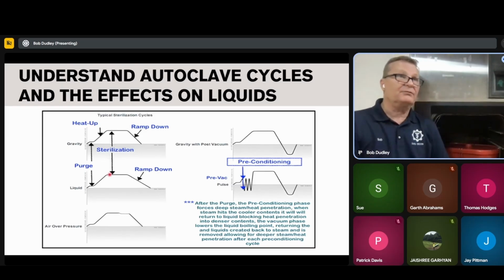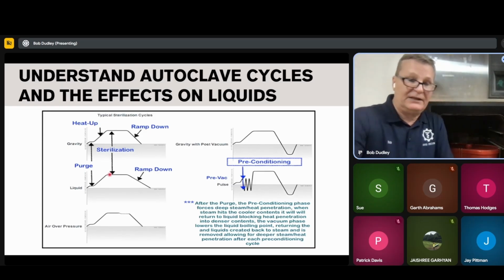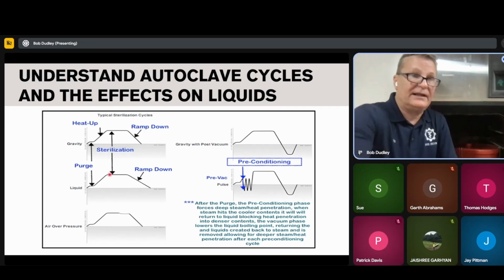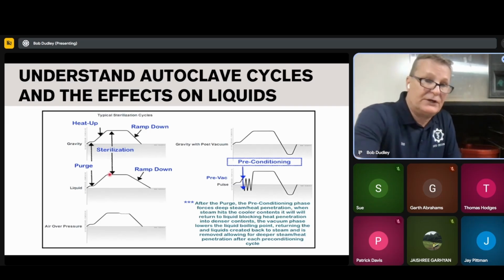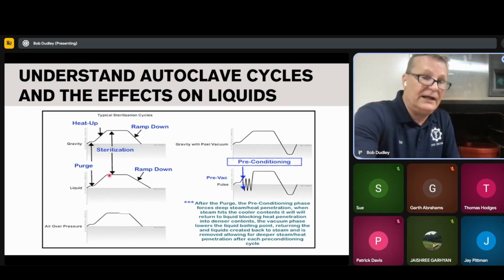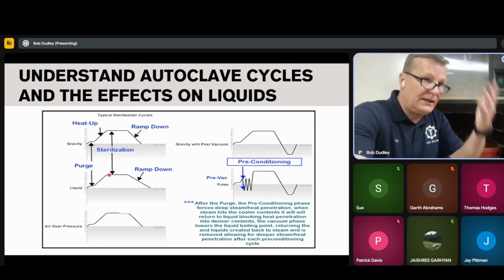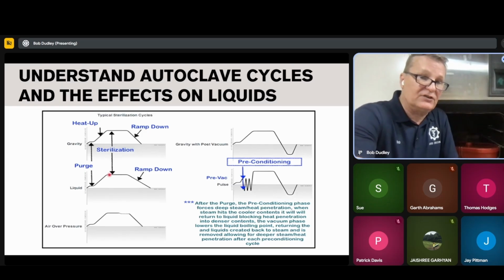And a lot of places I go in and they fight us like, Bob, I get a heat temperature failure or a pressure failure, and then you open it up, let's see how you're loading it, and they have it stacked to the gills because it's Friday and the technician is 19, 20 years old, and they don't want to sit there all night, so they overload the autoclave, and then they end up getting a failure, and then they end up having to restart the whole thing over again.